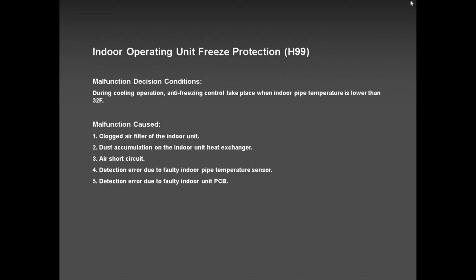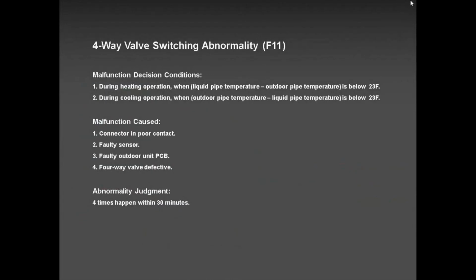H99, I have seen that during summertime. A lot of people like using dry mode. Dry mode is okay, guys, no problem. You can use dry mode. But remember, you need humidity levels of above 80% to use it. So I would say dry mode is good for tropical areas, hot areas, really warm areas. Because when you are operating the unit in dry mode, and once the humidity levels are under control, the coil tends to get very, very cold because the indoor fan is at super low speed. So the coil gets super cold, and as the temperature gets below 32 degrees Fahrenheit, at least 3 to 4 times in an hour, your H99 will pop up. So that could be the case if you are telling me the system has no problems with refrigerant.